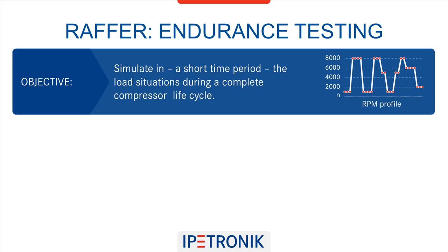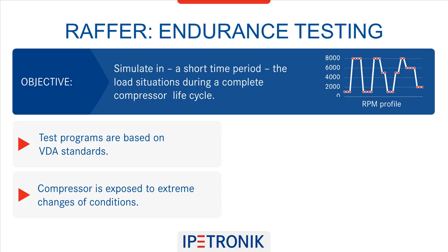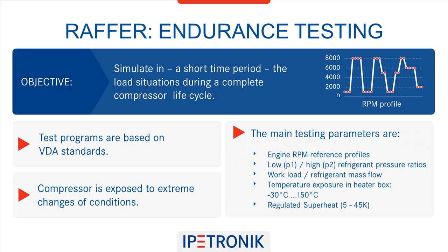With the RAFFER test, we can simulate, in only 200 hours, the overall stress profile of a compressor's entire life cycle. The RAFFER test is based on VDA standards and is a mandatory test procedure for every OEM compressor manufacturer. During the test cycle, the compressor is exposed to extreme changes in operating conditions, which are controlled by the IPE Motion Test Program, providing information on various RPM profiles, different high or low pressure ratios, extreme changes in workload and refrigerant mass flow, variations in ambient temperatures within the heater box, ranging from -30 degrees to up to 150 degrees Celsius, and different levels of superheat in the range of 5 to 45 degrees Kelvin.